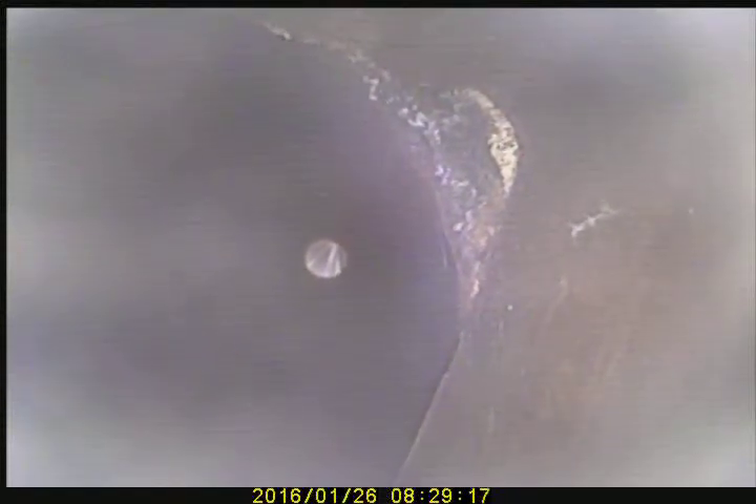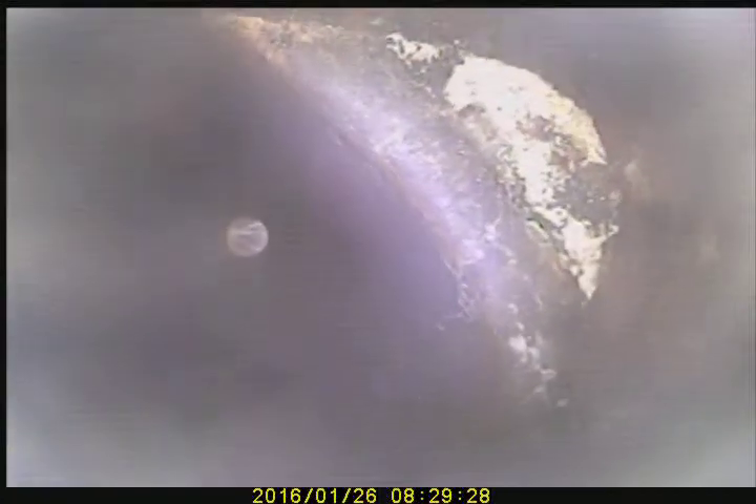There it goes — that's where it makes the transition. This is where we go from a 12-inch round flue to the 13x13 flue. The transition is not smooth. You can see there are some gaps, some inconsistencies where it steps outward. It was not parged smooth. This may affect drafting. We do have a significant stagger from the 13x13 to the 12-inch round.